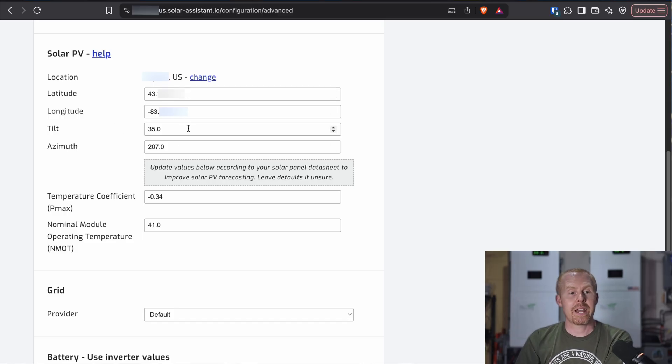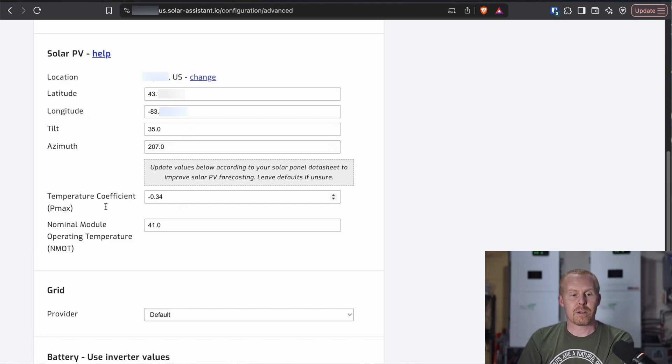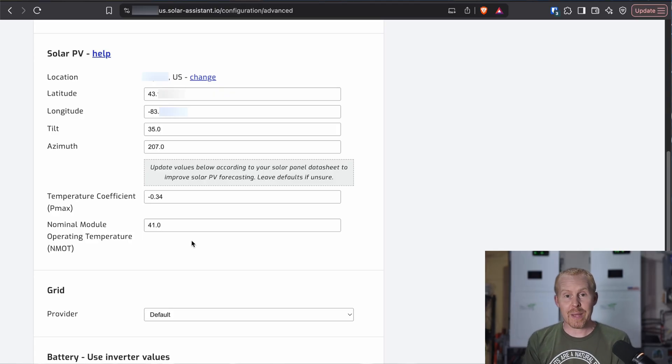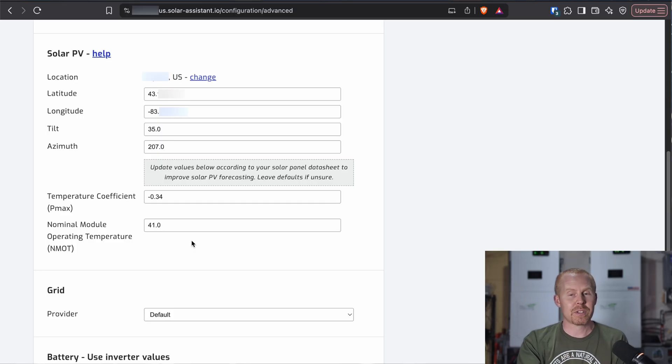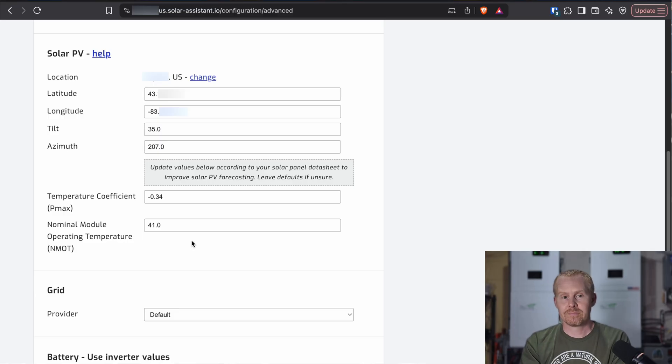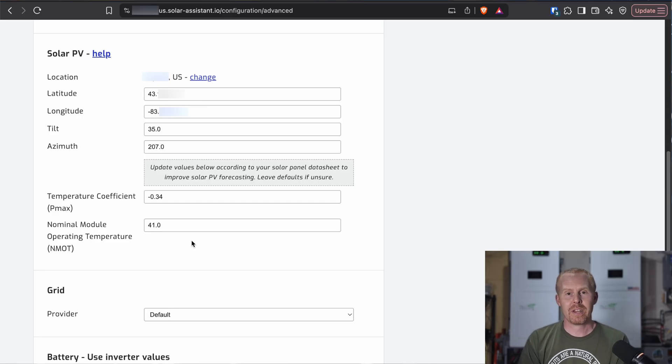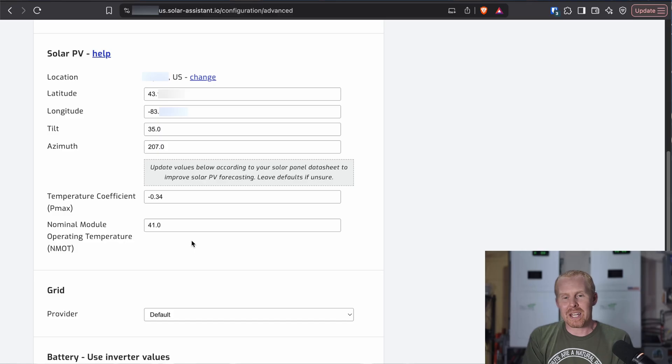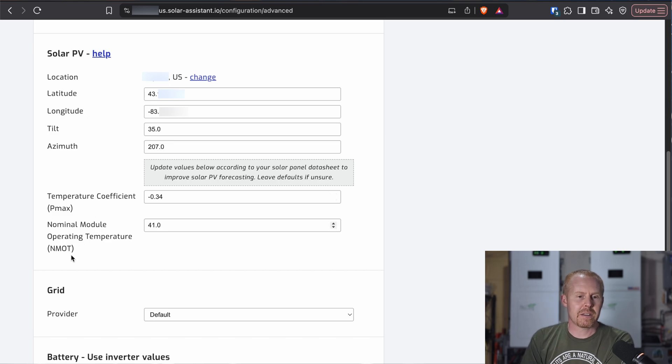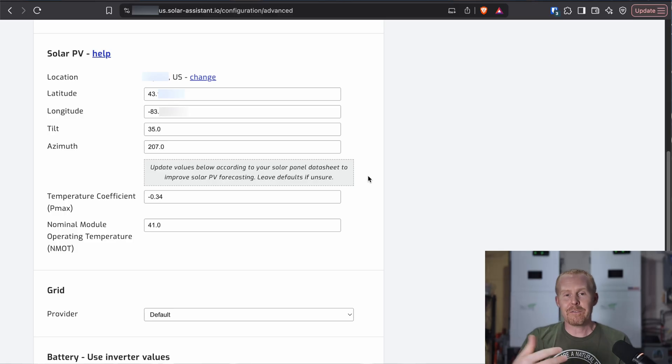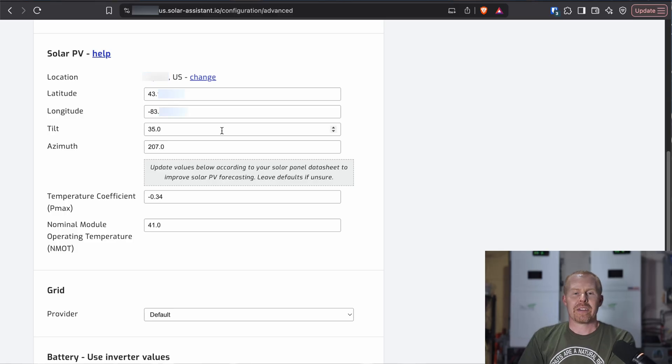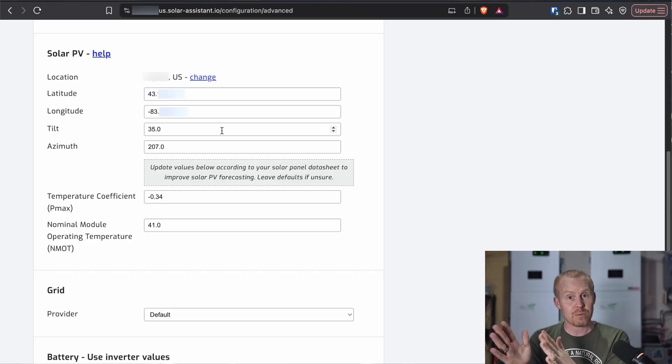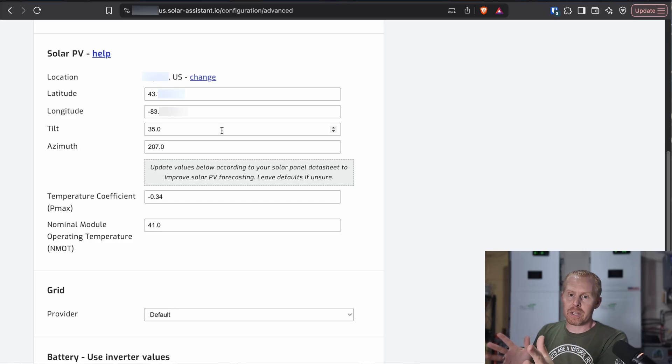And then you need to go through and add your tilt azimuth, your temperature coefficient, your nominal module operating temperature for your specific range of panels. Now, keep in mind that this is only able to be set for one direction. So if you've got a west-facing array and an east-facing array, you can't set one value for both and have it track both. You really just have to pick the array that probably is going to be producing the most for you. And they give you this little note regarding the temperature coefficient and the nominal module operating temperature. If you have the information, update them. Otherwise, leave them alone. But then the tilt and the azimuth is going to be what angle do you have your panels set to? And then the azimuth is going to be the direction that they are facing.